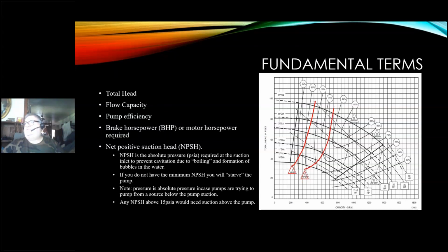So each one of these lines represents a different curve. In this case, net positive suction head of 8, 10, 15, 20. If you have a problem in the field, you have to have the minimum pressure pushing water into the pump, and that's where these lines come in. Otherwise, your pump will starve, and I have had more pumps show up where the pressure differential, the head, shows fine, but you're not getting the flow. So the pump can fool you into thinking, hey, I've got the right pressure, discharge, and suction pressure difference, but I don't have enough water, and this is why.